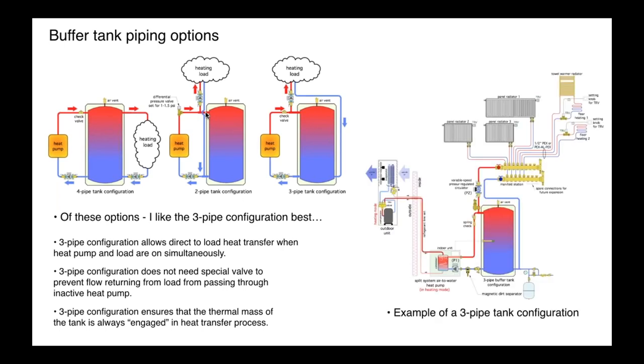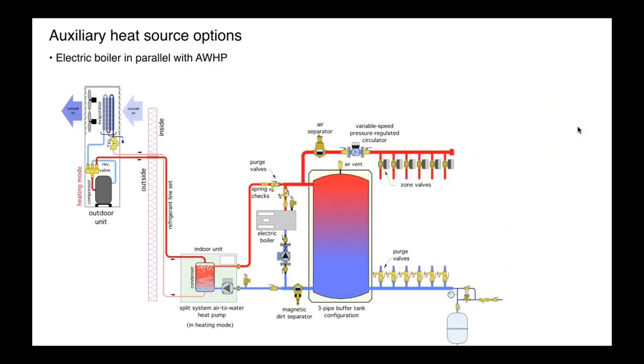So here's an example. This is right out of Hydronic 27. Split system, air water heat pump supplying a buffer tank. We're coming off of that. It's a three pipe configuration. We're going to a manifold, and we have a combination of panel radiators, a towel warmer, some floor circuits. Do whatever you'd like. Keep the water temperature low and zone to your heart's content, because that buffer tank is your friend keeping that heat pump from short cycling.